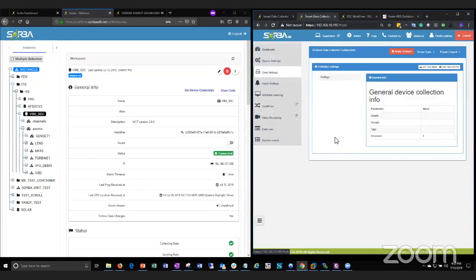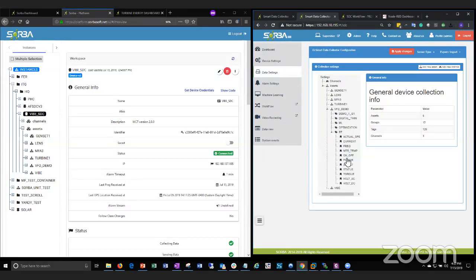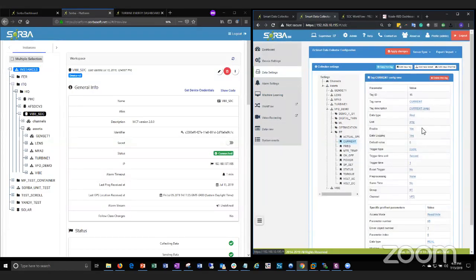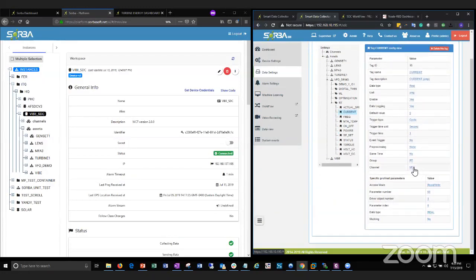You configure the Sorba itself, set up the tags, and within the tags you set up an asset with some tag groups. Then, just like a SCADA system, you set up a tag. Here I'm setting up a current, and I'm telling this tag to pull that piece of data once a second. This particular one is tied to, I'll show you in the channel here, a Siemens sinamics drive.